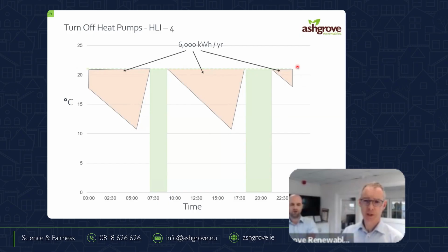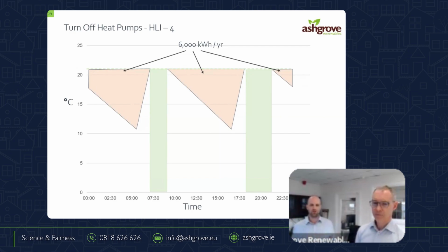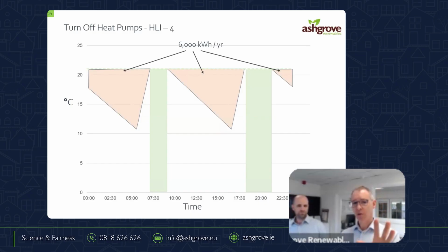Yeah, whereas the previous gas graph was €25 over the course of the year, that's, I don't know, €600 over the course of the year. Yeah, and inevitably, of course, in this building as well, my radiators are probably maybe undersized. Efficiency drops and so our running cost goes up. Yeah. All we're saying is, and it's one of the main reasons we're doing these presentations, for God's sake, turn the heat pumps off if they should be turned off. If you would turn it off in the case of oil, turn it off in this case.